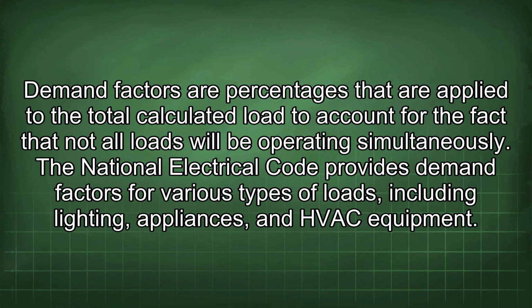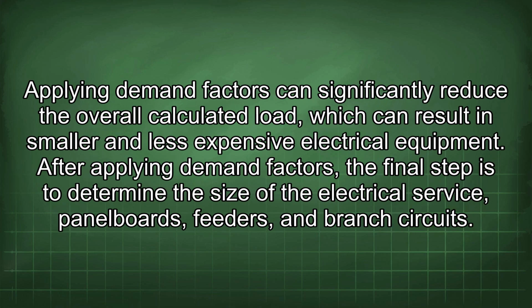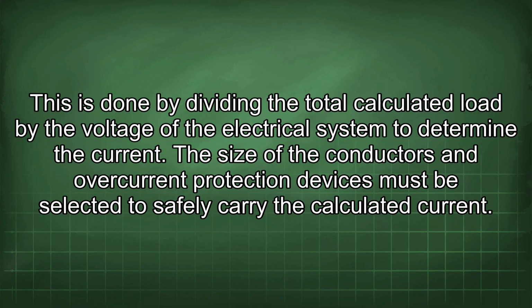The National Electrical Code provides demand factors for various types of loads, including lighting, appliances, and HVAC equipment. Applying demand factors can significantly reduce the overall calculated load, which can result in smaller and less expensive electrical equipment. After applying demand factors, the final step is to determine the size of the electrical service, panel boards, feeders, and branch circuits. This is done by dividing the total calculated load by the voltage of the electrical system to determine the current. The size of the conductors and overcurrent protection devices must be selected to safely carry the calculated current.